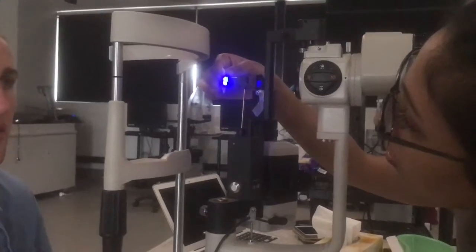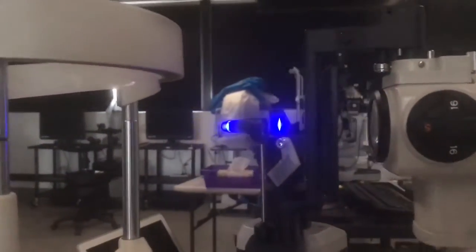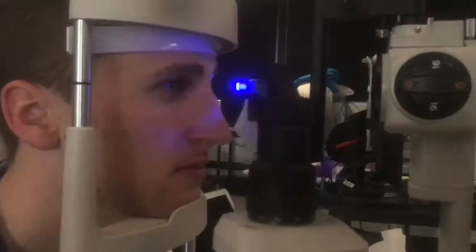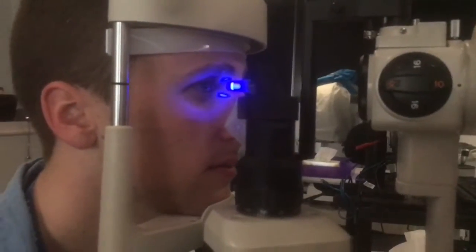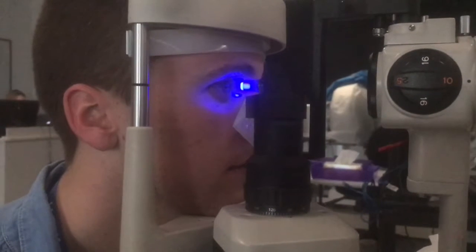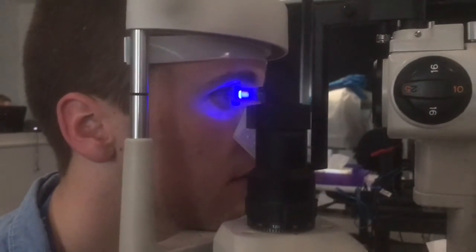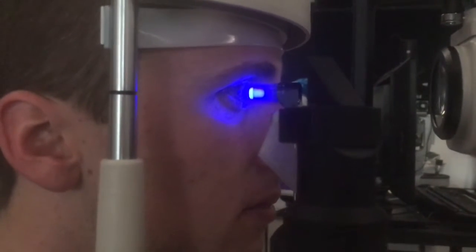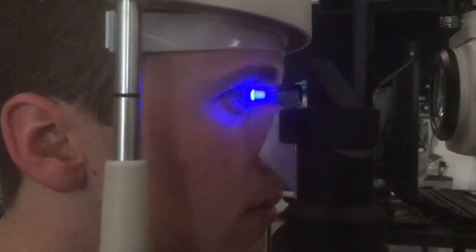The probe of the tonometer is cleaned with an alcohol wipe and left to dry. So the tonometer is moved slowly until the prism rests gently on the centre of the patient's cornea. And with the other hand, you're going to turn the calibrated dial on the tonometer clockwise until the two fluorescein semicircles make a horizontal S-shaped pattern.